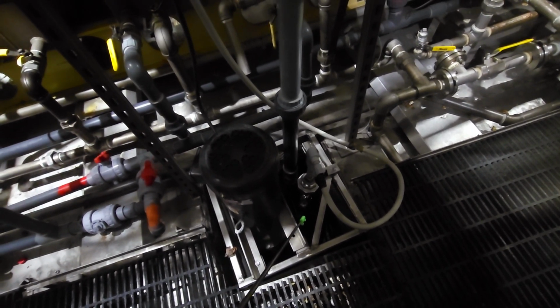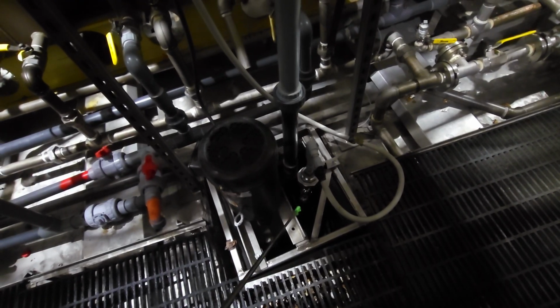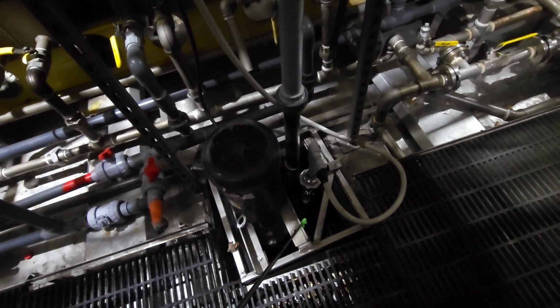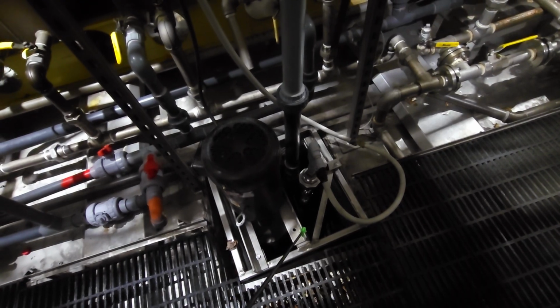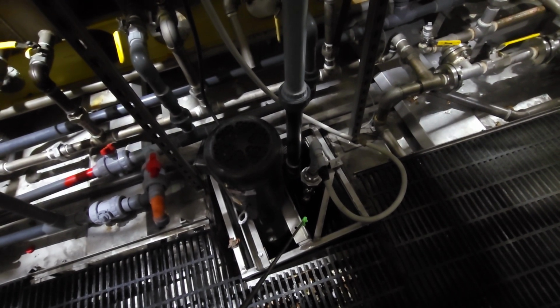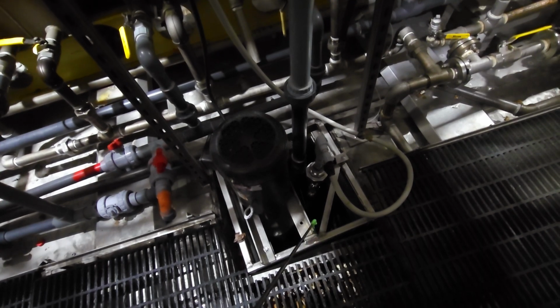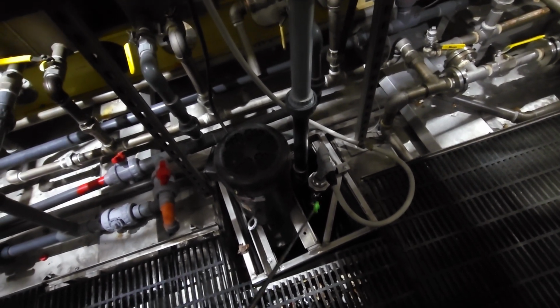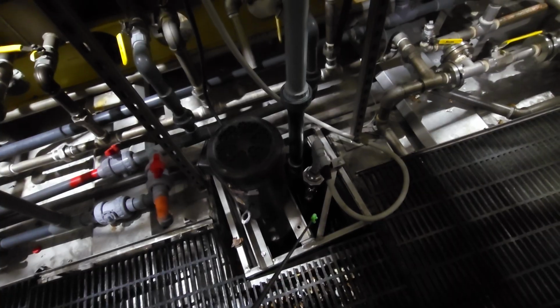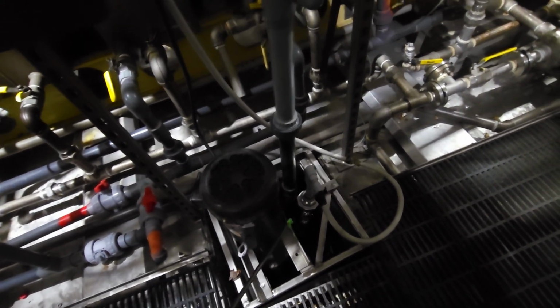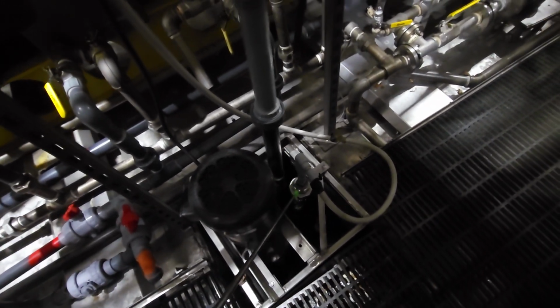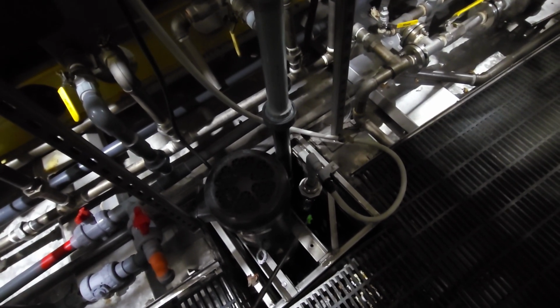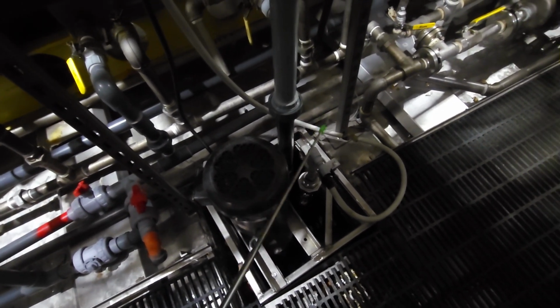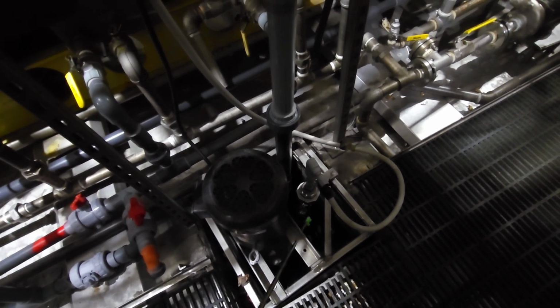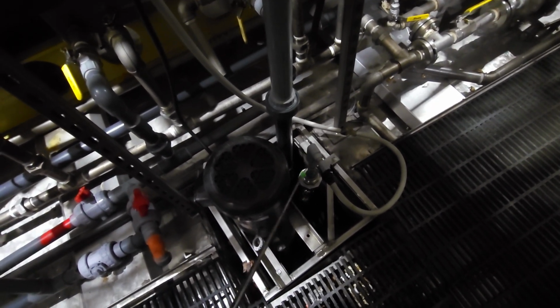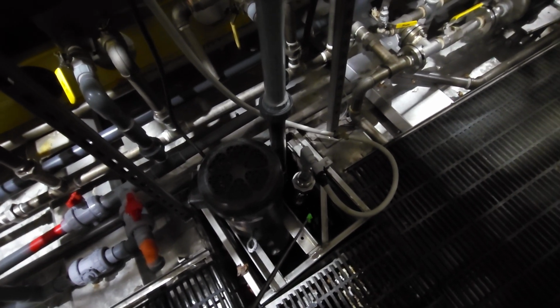These floats work when they're normally closed. When they're open, when the circuit's open, it tells the PLC to turn on. We do that so if they all fail or if something fails, they just run. Your top float is your alarm. That's all that's for. That sets off the alarm and says, hey, I got too much water in me. It'll also kick the pump on. Most likely the pump's not working if that alarm's going off. Because if your 2 floats both are stuck down, it's very rare.